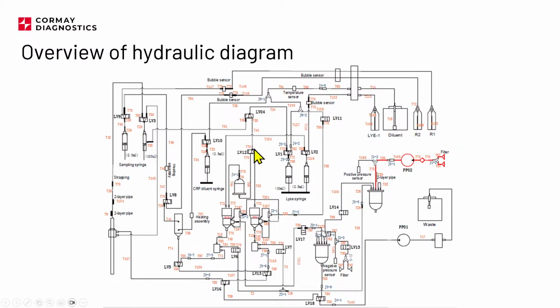The lyse is not warmed up, but the volume of lyse is just a few hundred microliters. I think it's like 200 to 300 microliters of lyse that is added to the chamber during the measurement. And the amount of diluent is like half a milliliter or even more. So if the diluent is warm and the volume of lyse is smaller, it means that the temperature in the chamber will be higher. So the reaction will be correct. So this is the reason for having a heater on the WBC. It's not necessary for RBC because we are not destroying red blood cells. Reagents have a temperature range in which they are working. So this is the reason why we have a heater.